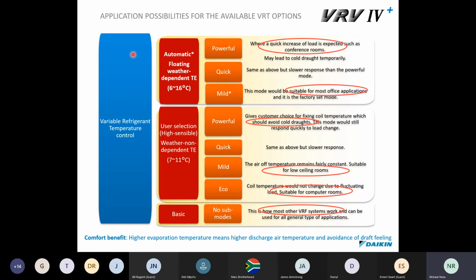So what will happen? Maybe the expansion valve will close off in the office if it's met temperature, or it will be open maybe 5% or 2% or 3%, whatever the need may be. And then the conference area will open at 100%, but it doesn't just open bang 100%. Because of VRT, it opens slowly, so it'll open incrementally, so you still achieve your comfort, because it's a worse feeling to cool a room down immediately because it becomes uncomfortable. Then also you give the customer a choice for fixing the coil temperature, which should avoid cold draft.